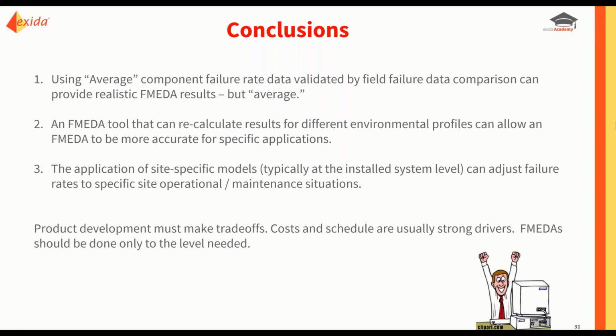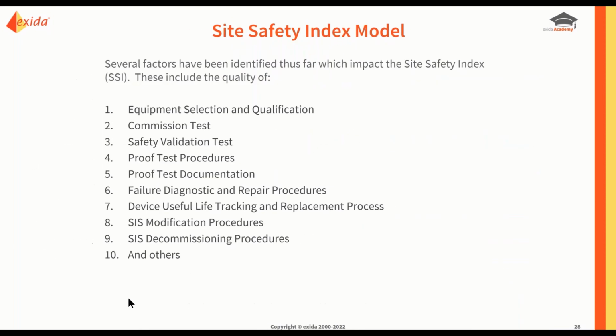As you can see, if you're designing a project for functional safety, you basically have no choice. Well, there are many ways. You can use field failure data, but what if it's a new design? You've got to do something to generate failure rate predictions as a function of failure mode if you are involved in a design for functional safety, IEC 61508 or ISO 26262 for automotive. So those are the ways in which I would evaluate a client's needs. And if they just don't care about any of these things, then we don't have to go beyond a qualitative FMEA.